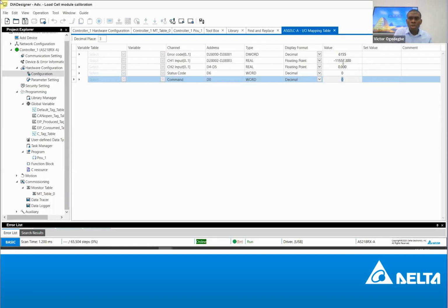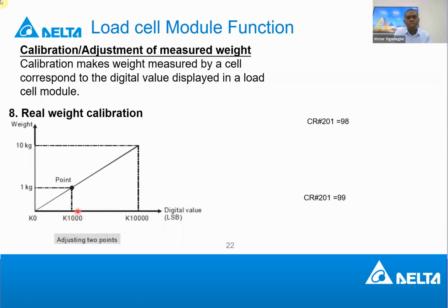So for you to have a number that corresponds to your real weight from the sensor, that's why we need to do this calibration, so that we have a correct digital value that corresponds to the analog value coming from the load sensor. So you do that with calibration.